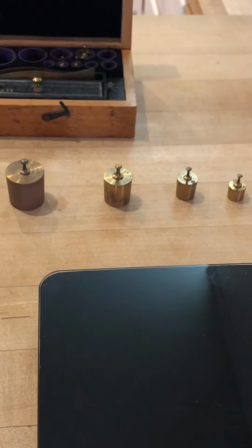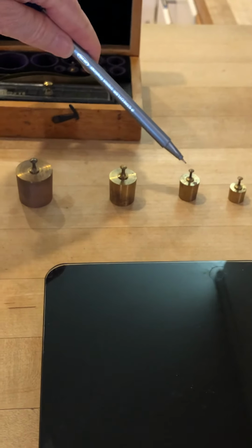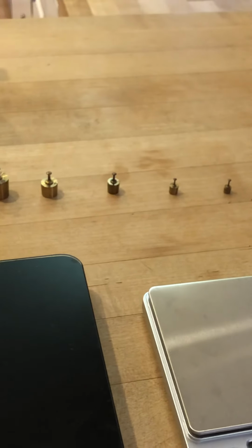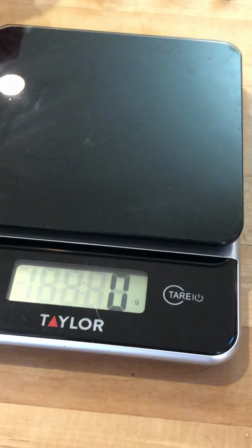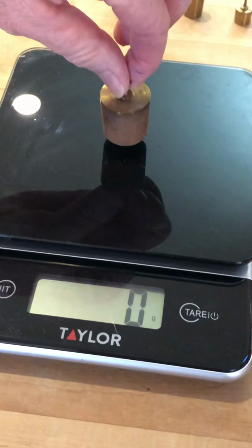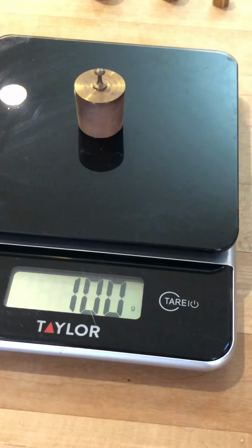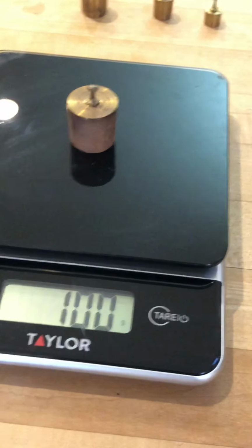So I'm going to write down some measurements here, and what we're using are some standard weights. These are used to calibrate things. This is 100 grams. This is 50. This is how many? 20, 10, 5, 2, and 1 over there. And let's just see what I get when I weigh them. So starting with the 100 gram weight, I'm putting this in what seems to be the sweet spot for this balance. And it tells me I have 100.0 grams. And we're going to come back to that later.